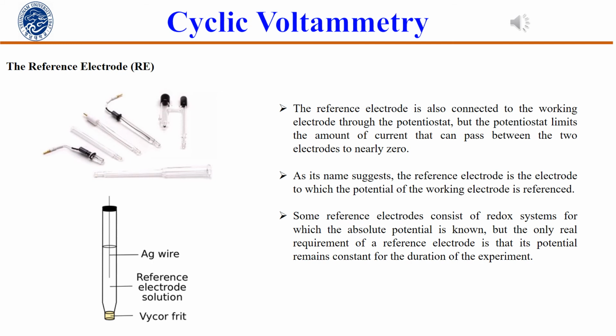Commercially available aqueous AgCl reference electrodes should be stored in the dark and submerged in a solution identical to the solution inside the reference electrode. Usually we use potassium chloride. Old AgCl electrodes can develop a white buildup on the wire and may drift away from their reference potential.